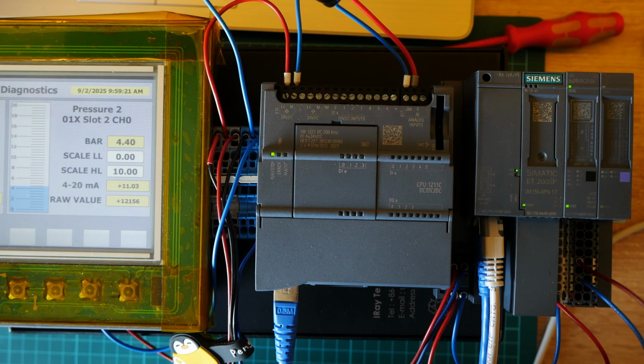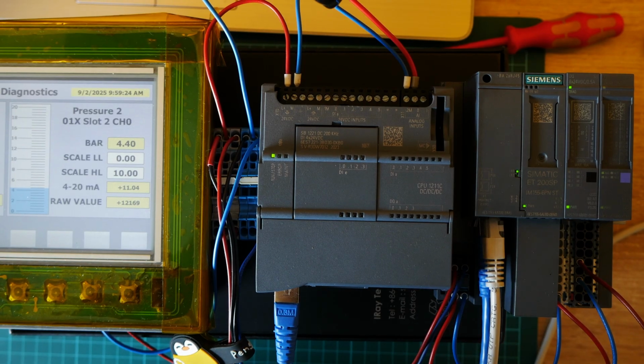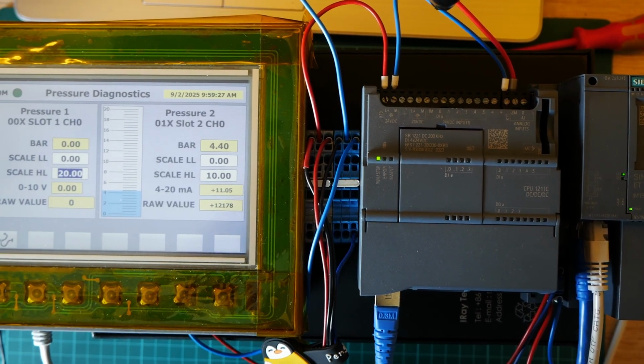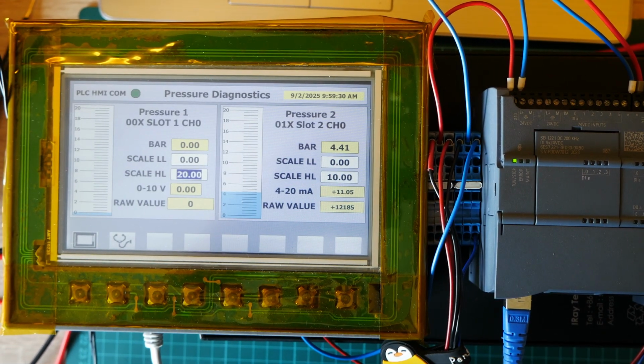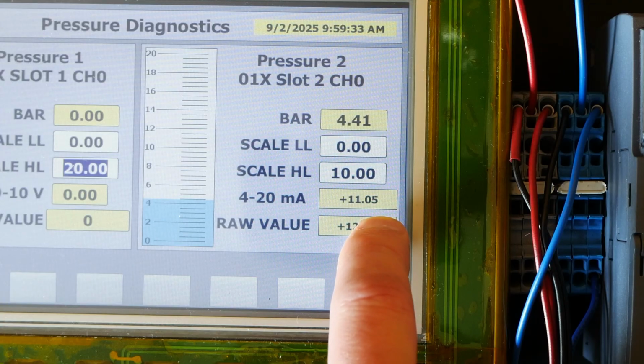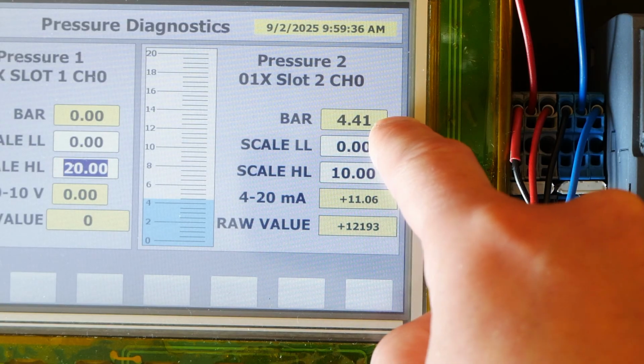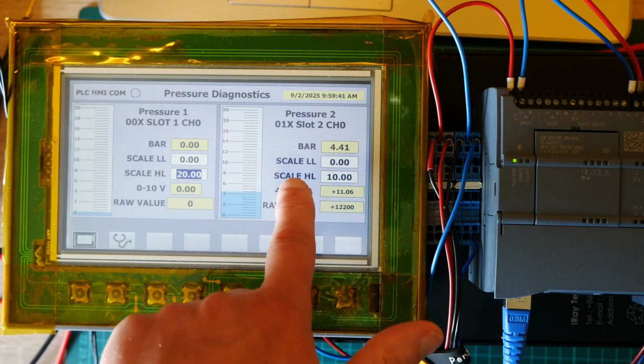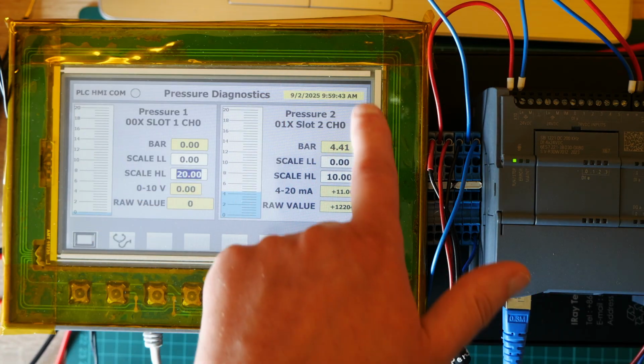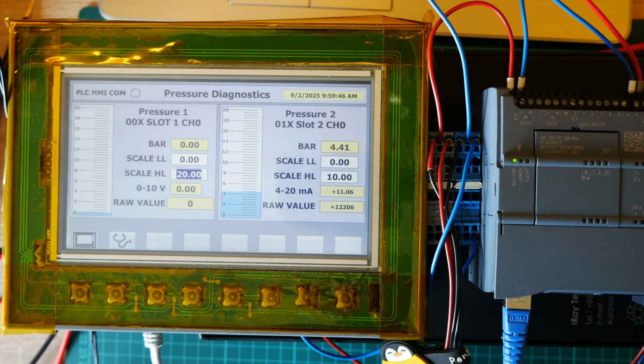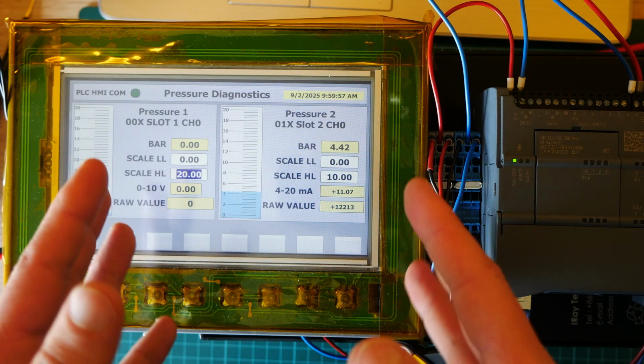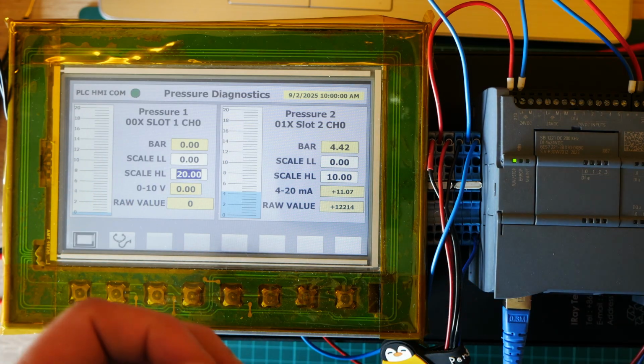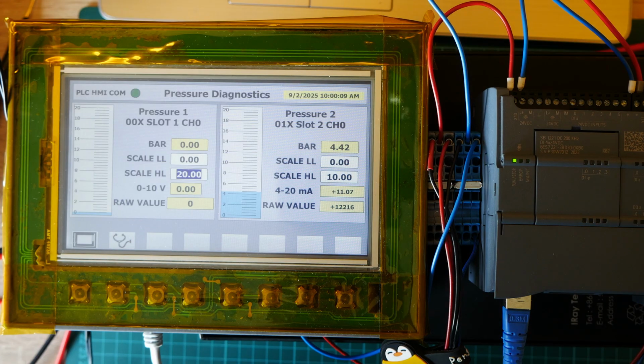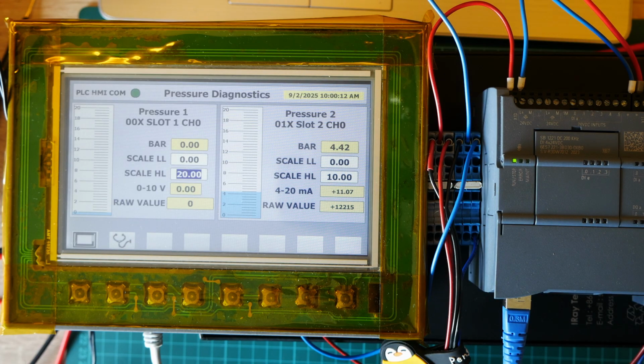So I do that, and we can scroll to our HMI. As you can see, we have 11.05 milliamperes, and this is our bar reading, because this pressure sensor is from a 0 to 10 bar scale. So that is correct. This could give us a good indication that the program is working fine and the analog input card is working fine. Put in a resistor and you can check it like that.